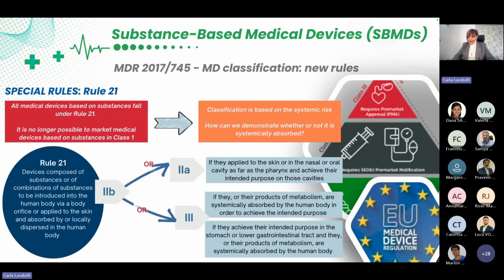For ophthalmic devices, Rule 21 is particularly important because it helps us distinguish products that act only on the ocular surface from those that may penetrate deeper or even reach systemic circulation. And depending on the risk profile, these products may fall into class 2b or 3. So, ultimately, the classification is driven by the intended purpose and how deeply the substance, the device, needs to reach to achieve the intended purpose, which naturally leads us to the key question: how do we demonstrate whether or not a systemic absorption occurs?